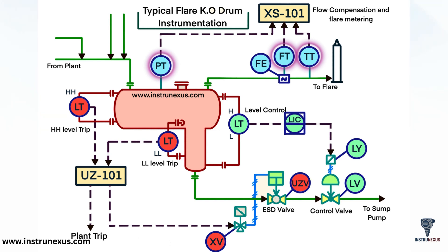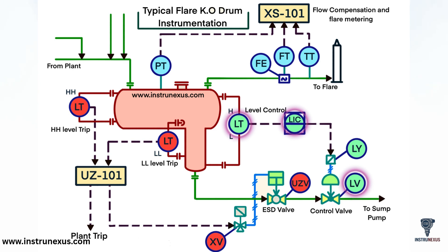For level control, the drum has level transmitters (LT) that continuously sense the liquid level. Their signal goes to the level indicating controller (LIC), which adjusts the control valve (LV) through the positioner (LY) to maintain the liquid within the desired range. The drained liquid flows onward to the sump pump.